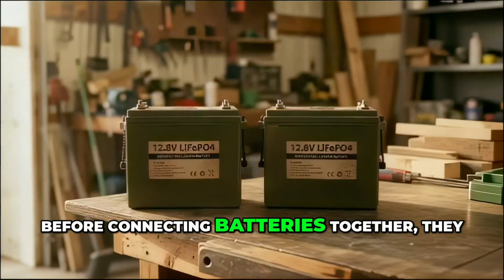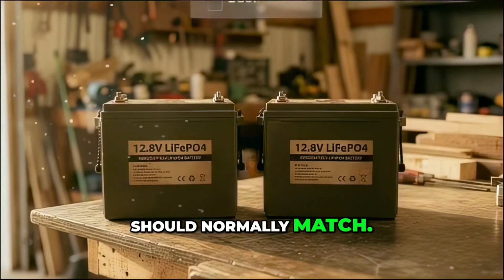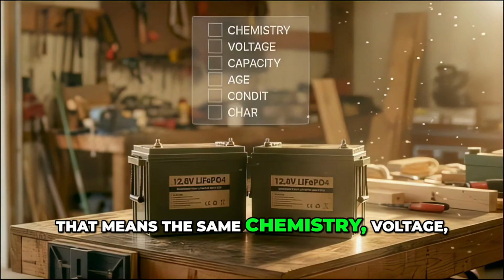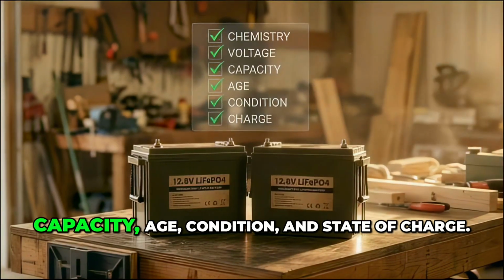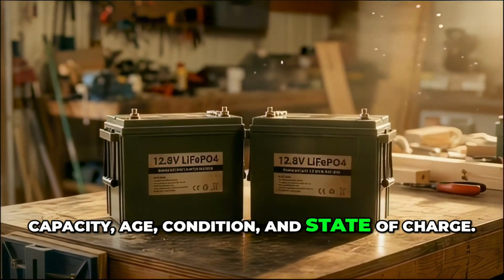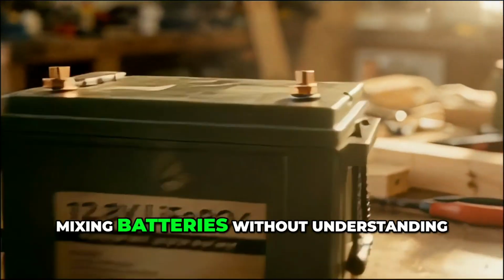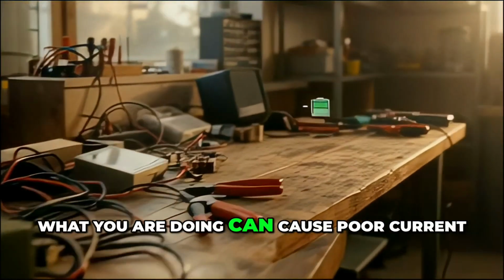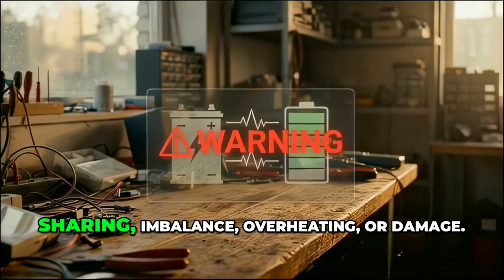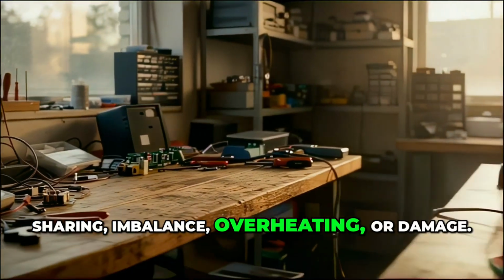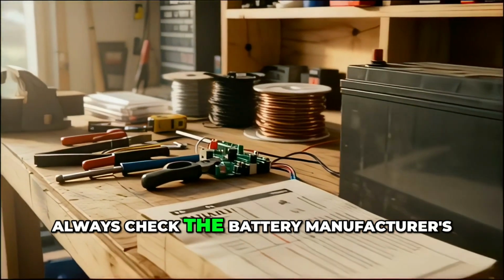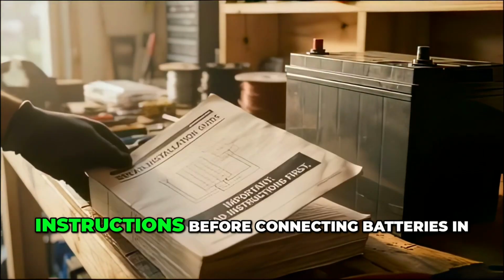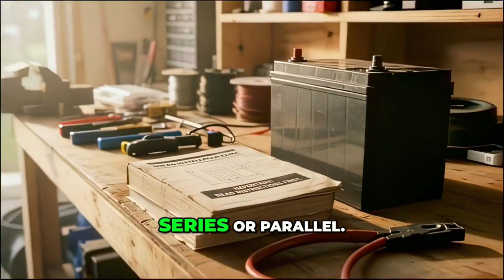Before connecting batteries together, they should normally match. That means the same chemistry, voltage, capacity, age, condition, and state of charge. Mixing batteries without understanding what you are doing can cause poor current sharing, imbalance, overheating, or damage. Always check the battery manufacturer's instructions before connecting batteries in series or parallel.